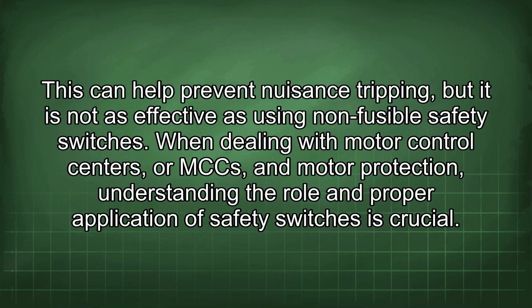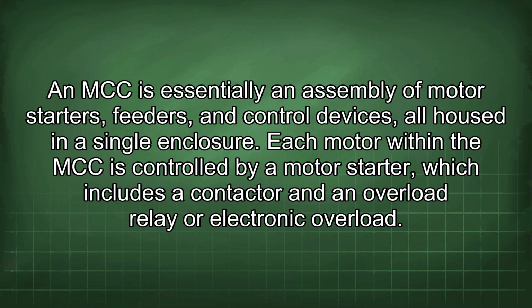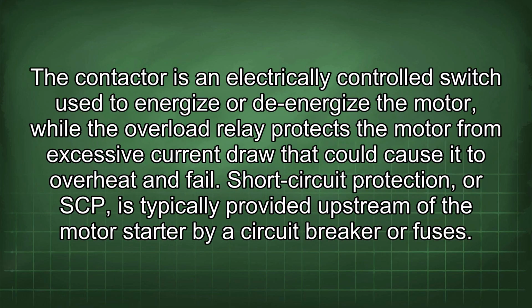When dealing with motor control centers, or MCCs, and motor protection, understanding the role and proper application of safety switches is crucial. An MCC is essentially an assembly of motor starters, feeders, and control devices, all housed in a single enclosure. Each motor within the MCC is controlled by a motor starter, which includes a contactor and an overload relay or electronic overload. The contactor is an electrically controlled switch used to energize or de-energize the motor, while the overload relay protects the motor from excessive current draw that could cause it to overheat and fail.